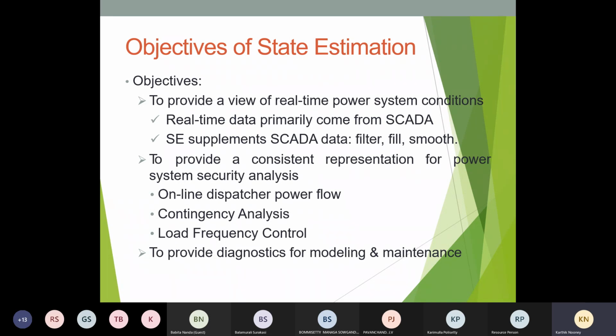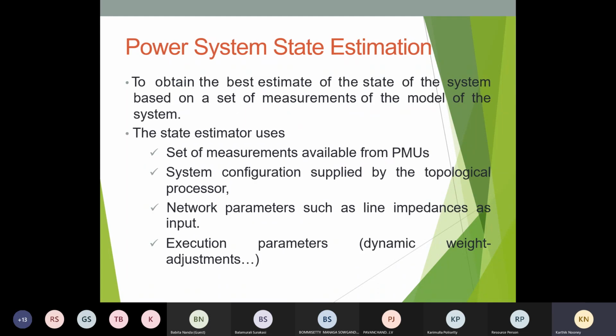Another objective of state estimation is to provide diagnostics for modeling and maintenance of the power equipment that are present in transmission system or distribution system. To obtain the best estimate of the state of the system based on a set of measurements, the state estimator uses the measurements available from PMUs and system configuration supplied by topological processor, and depends upon network parameters such as line impedances and execution parameters such as dynamic weight adjustments.